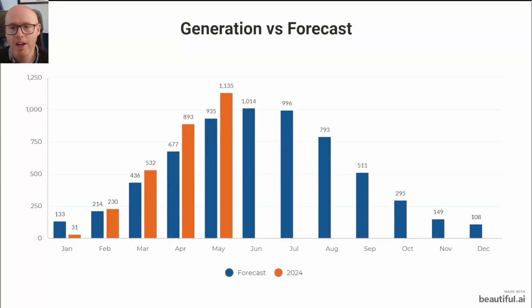Here's how it stacks up against forecast: we were forecast for 935 kilowatt hours and we are happily beating that. Our southeast array is performing exactly as expected from the forecast in PVGIS and OpenSolar, but our northwest array is outperforming by quite some margin — that's where we're getting the big gains.